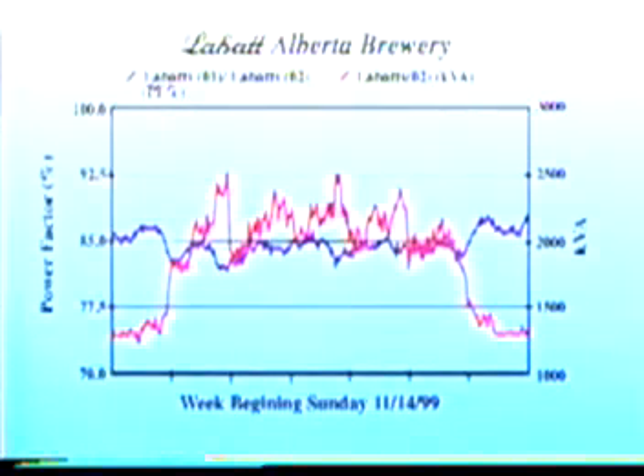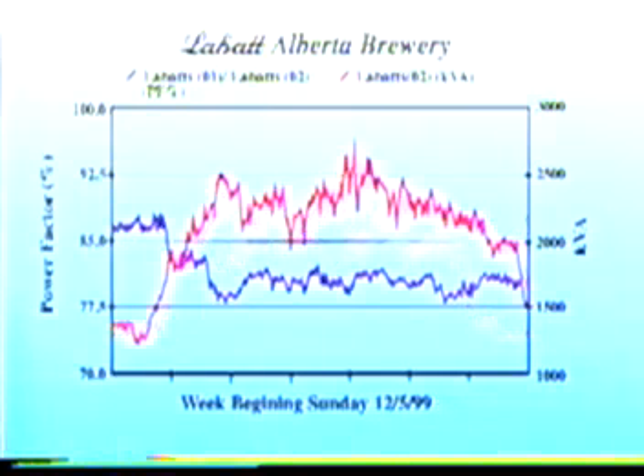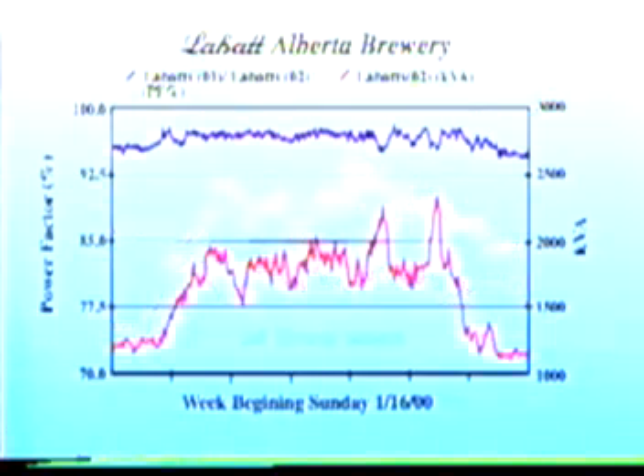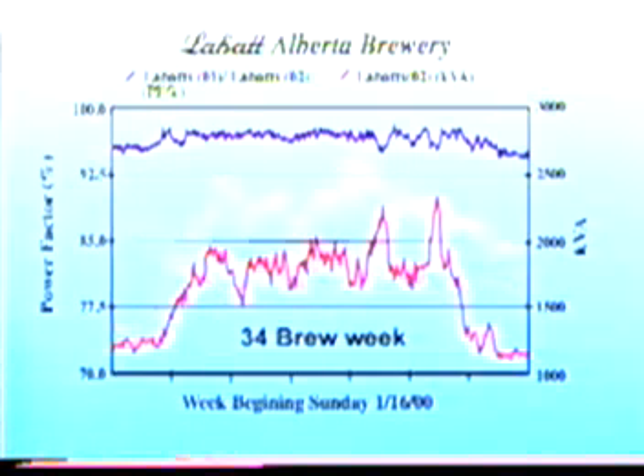Our first graph shows power factor and kVA for a week in November where we ran 31 brews. Our power factor was 85% and our kVA was approximately 2,000 to 2,500. Our second graph shows a week in the month of December where we ran with our capacitors off. Our power factor then was approximately 80% and our kVA was 2,000 to 2,700. The third graph shows a week in the month of January where we ran with our ElectroFlow units on. You'll see that our power factor jumped up to 95% with less fluctuations and our kVA dropped to 1,700 to 2,200, again with less fluctuations. So you can see from these graphs that we're getting the power factor and kVA improvements that we're looking for.